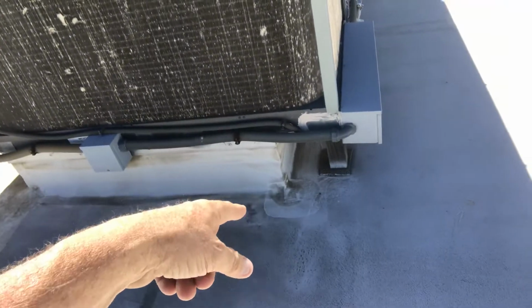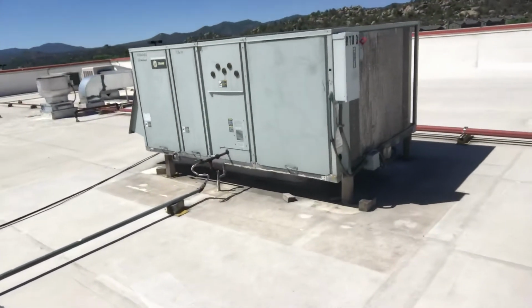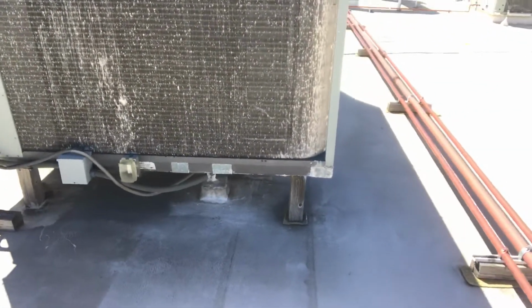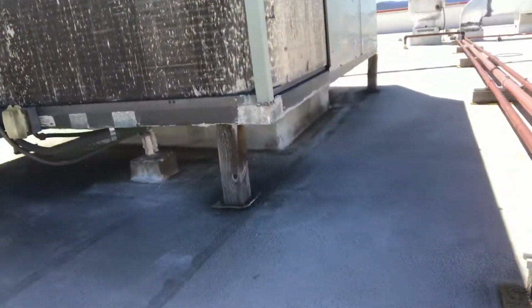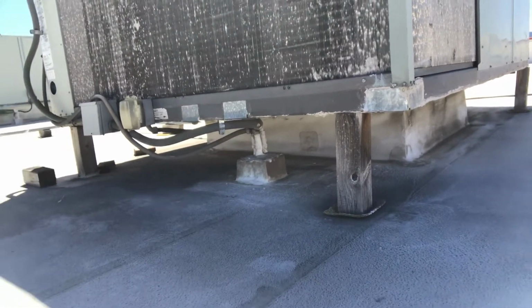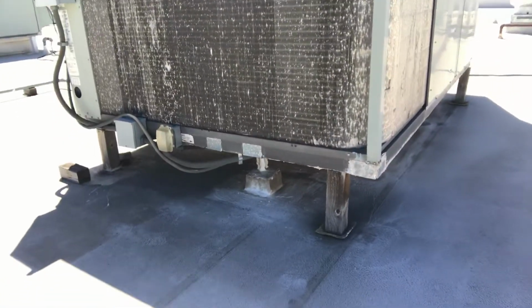You look at that right there. Wow, that's pretty bad. Look at this one. This one's even worse. It's a smaller curb, more blocking. More blocking was used. This is a horrible design. Not the way you want to go. You can really get down there and look at that block. And then you have this one holding it up. The electrical's tucked up underneath. That block over there. Look how small that curb is. It's just for the ductwork alone. That is not supportive. That is not right.